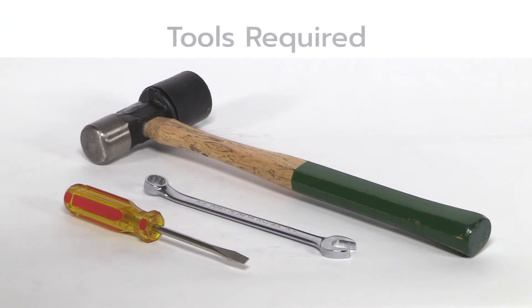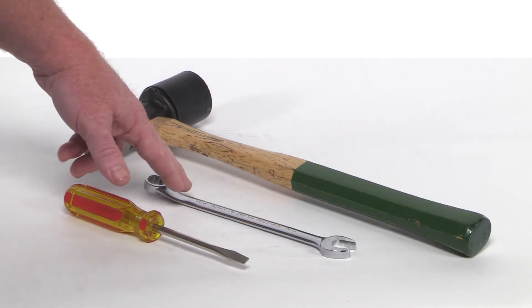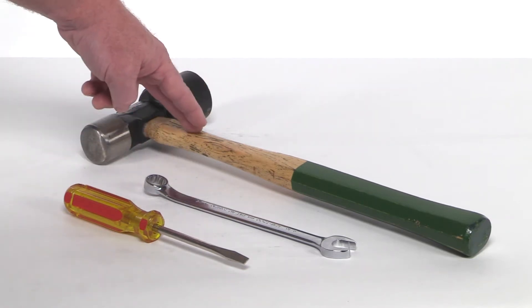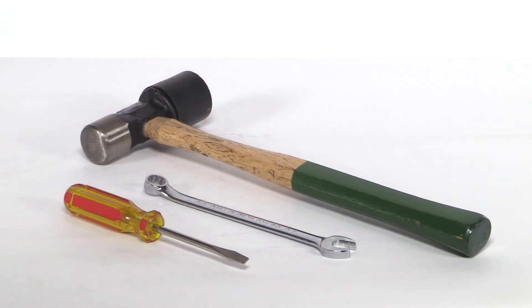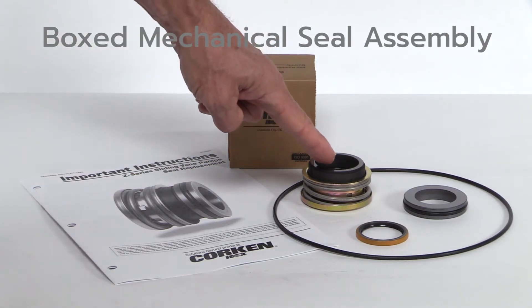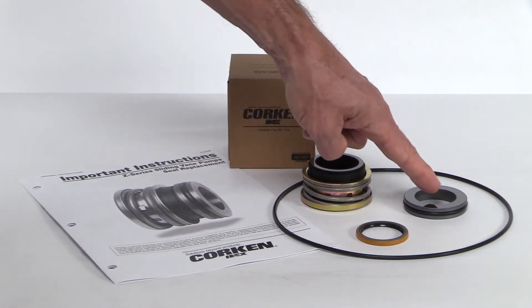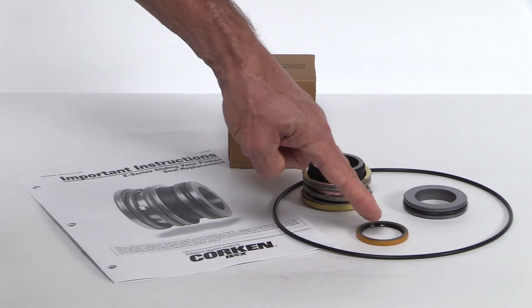Replacing the mechanical seal assembly in a Corken Z-Series sliding vane pump requires some basic hand tools: a flat blade screwdriver, a wrench (size will vary depending on model of pump), a hammer, and a can of spray lubricant or light oil with plenty of clean shop towels. The boxed mechanical seal assembly includes important instructions for seal replacement, a rotating seal with O-ring and seal retainer, a stationary seal seat with O-ring, a grease seal, and an O-ring for the pump head.